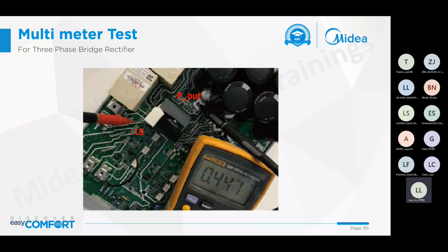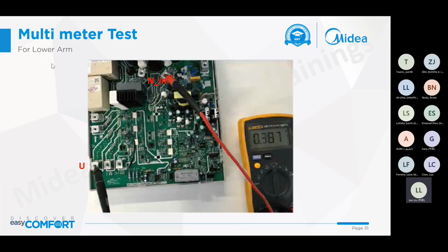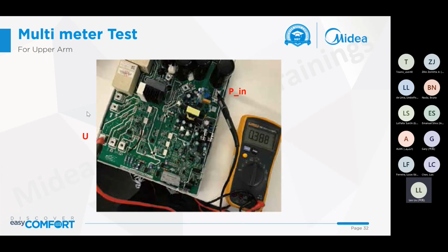Okay, we can use a multimeter to test the voltage. For example, we can test the voltage between this port P and L3. The voltage is usually around 450 voltage more or less, so this is normal. For the lower arms, we can detect the voltage between these 2 terminals; usually the voltage is around 380 voltage. In the upper arm, the voltage between them is also nearly 380 voltage.